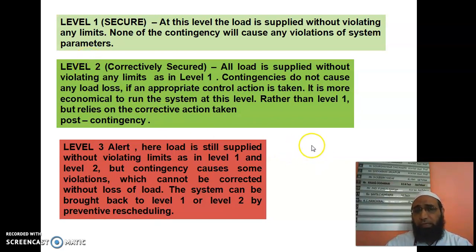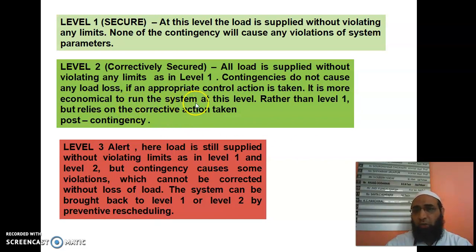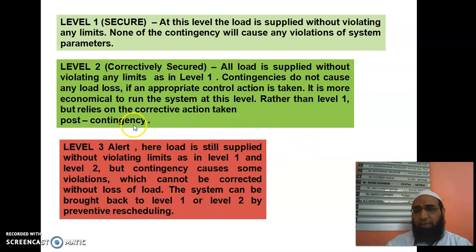Level 2 is also called the correctively secured level. All load is supplied without violating any limits, as in level 1. Contingencies do not cause any load loss if appropriate control action is taken. It is more economical to run the system at this level rather than level 1, but it relies on corrective actions taken after post-contingency events.